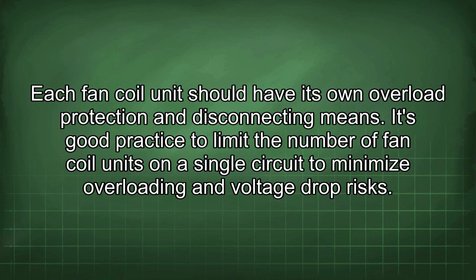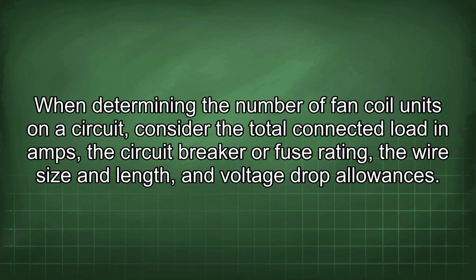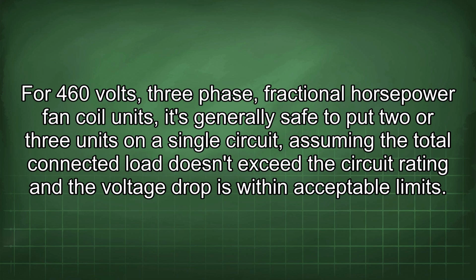It's good practice to limit the number of fan coil units on a single circuit to minimize overloading and voltage drop risks. When determining the number of fan coil units on a circuit, consider the total connected load in amps, the circuit breaker or fuse rating, the wire size and length, and voltage drop allowances. For 460 volts, 3-phase fractional horsepower fan coil units, it's generally safe to put 2 or 3 units on a single circuit, assuming the total connected load doesn't exceed the circuit rating and the voltage drop is within acceptable limits.